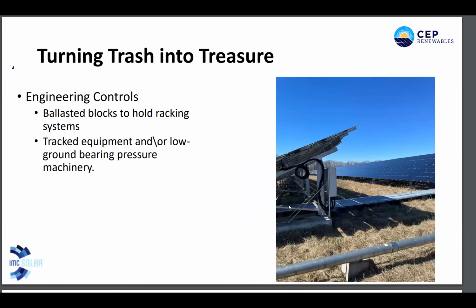So here's a picture. This is not the Mount Olive site. This is a site in Cleveland, Cuyahoga County. This was the first landfill solar project in the state of Ohio. But you can see the concrete ballasts there, and how the pipe chase here is all on ballast. Everything is above ground, including the fencing. Even the fencing around this, for electrical code, we have to maintain an 8-foot fence. Even that was on concrete ballast and not put into the cap. And you can see there, I've walked this site a few times and I haven't seen concerns about settlement and ponding of water here.